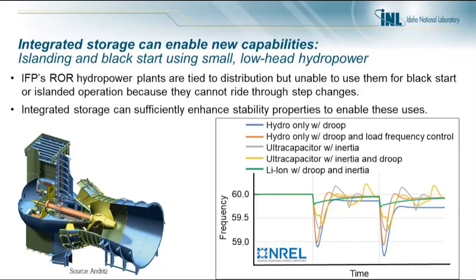This graph shows a set of simulations. The blue and orange lines are the hydro units only, with different control schemes, in response to step increases in load corresponding to the black start procedure. The gray, yellow, and green lines correspond to energy storage systems that could be hybridized with the existing plants and control options. Through the combination of hydro controls and hybridization, we're confident we can increase stability sufficiently to enable a distributed black start and islanded operation of the grid.